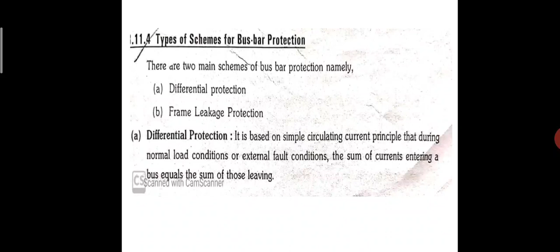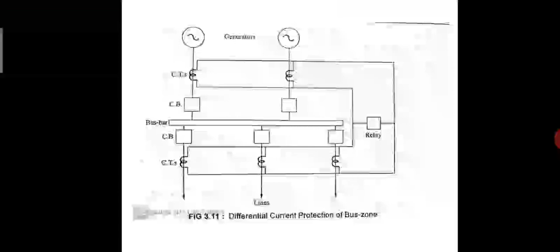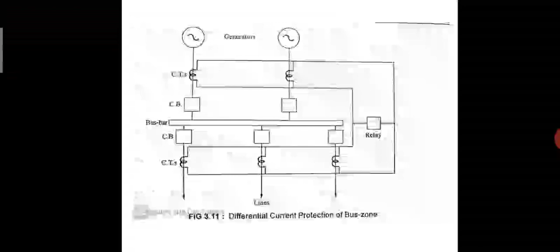So, see the circuit diagram. Differential current protection of bus zone. The top two are generators. This is the busbar. CT means current transformers, two parallel connected, each line one, and busbar below. Three circuit breakers, three current transformers and one relay are connected. This is the straight line busbar.